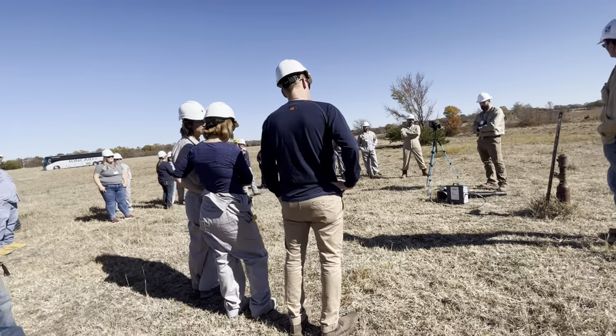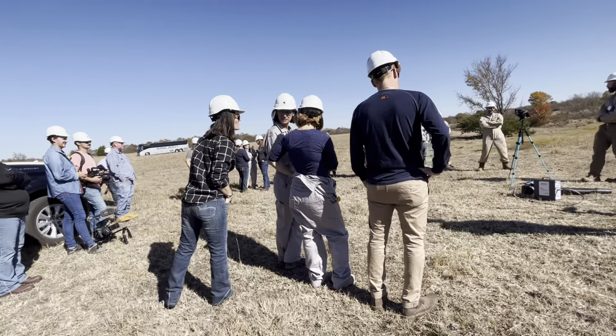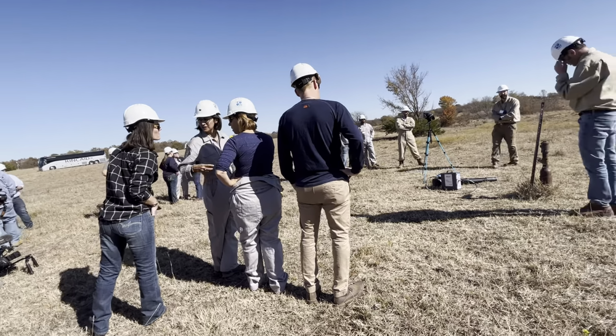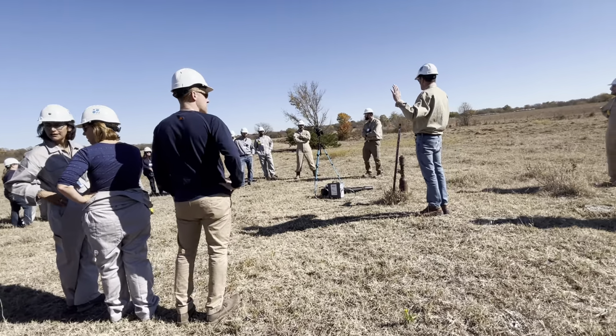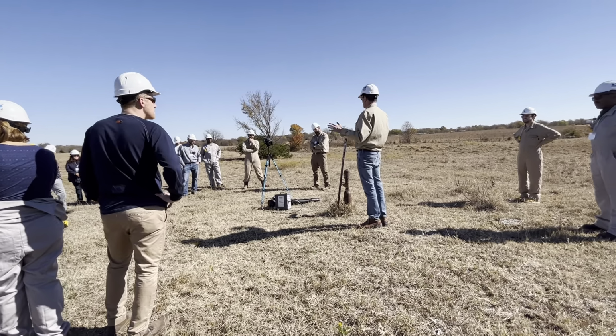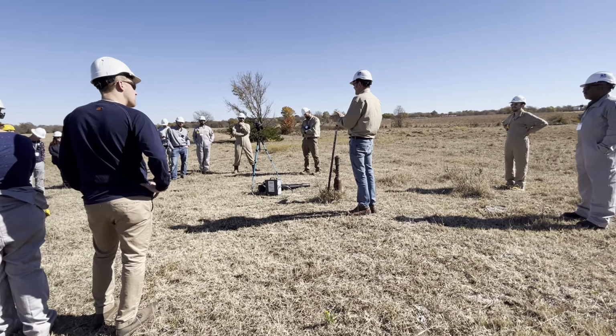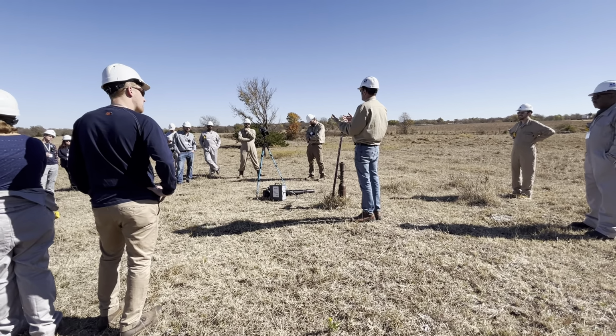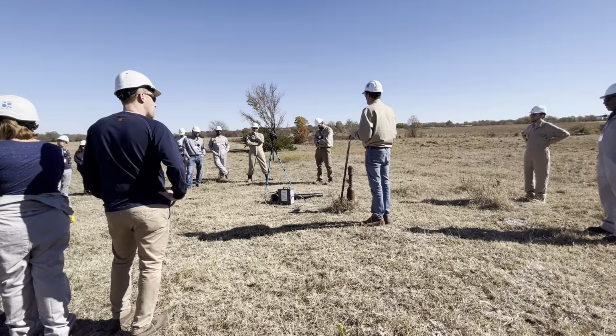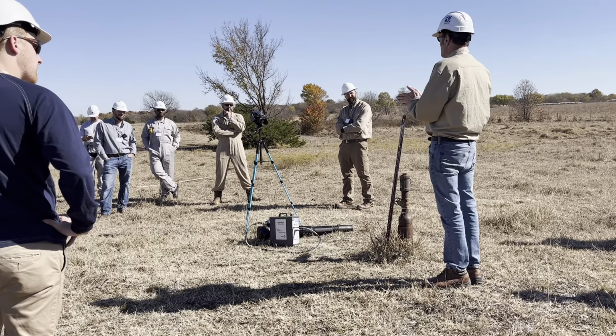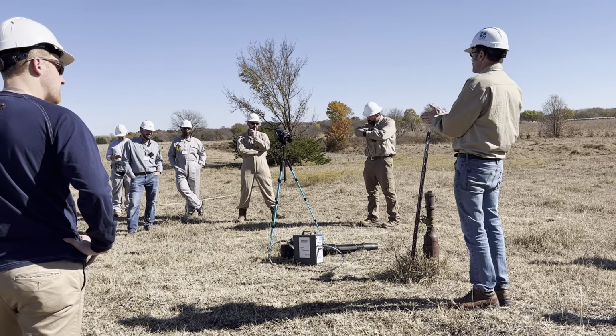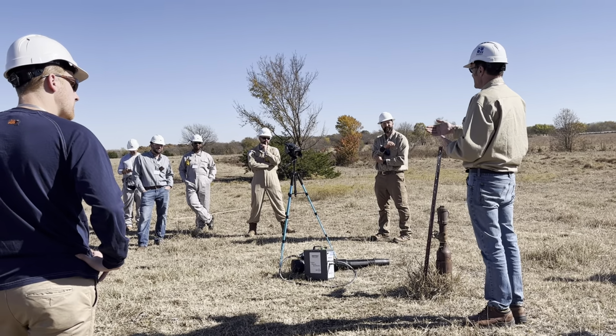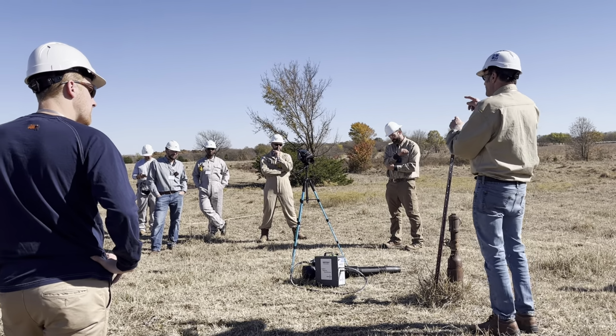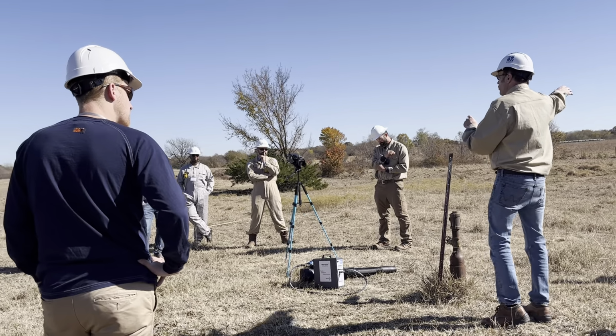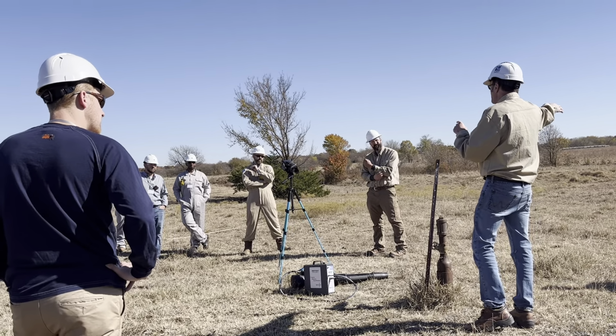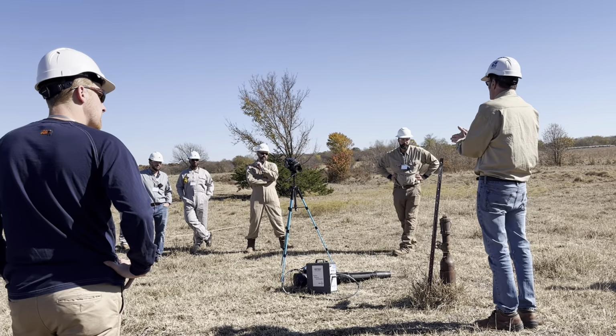Yeah, absolutely. To be clear, there's no calibration required. Oh, like once a year? That's separate, but that's a good question. The first one is, is there any calibration? What is a calibration? It's an adjustment of the instrument to read what you believe is right. If you know how to do it properly, your procedure should be that you don't calibrate until you've audited it. If you fail an audit, was it the last week, the week before, is all that data useless now? So you should never fail a calibration.